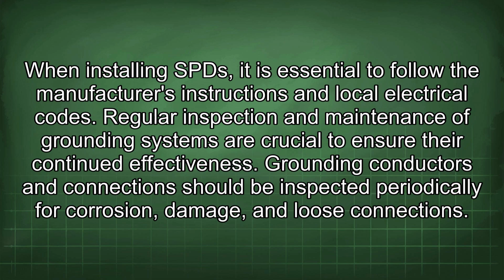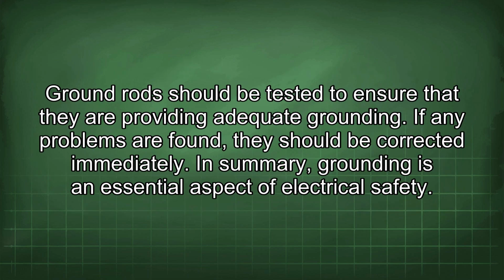Regular inspection and maintenance of grounding systems are crucial to ensure their continued effectiveness. Grounding conductors and connections should be inspected periodically for corrosion, damage, and loose connections. Ground rods should be tested to ensure that they are providing adequate grounding. If any problems are found, they should be corrected immediately.